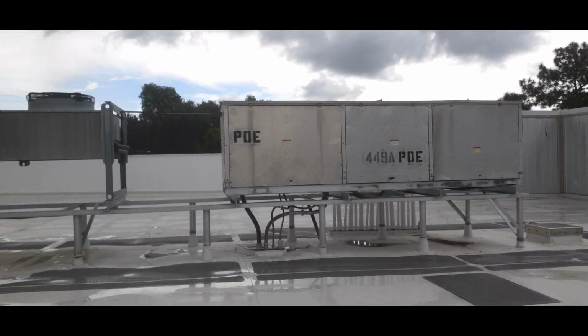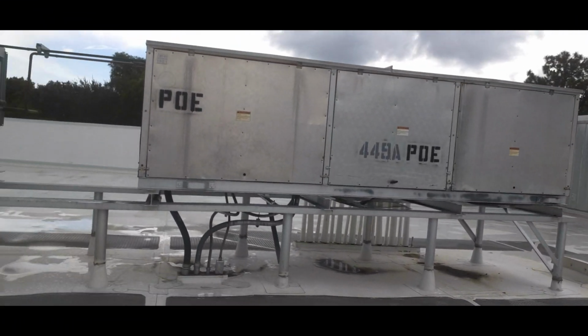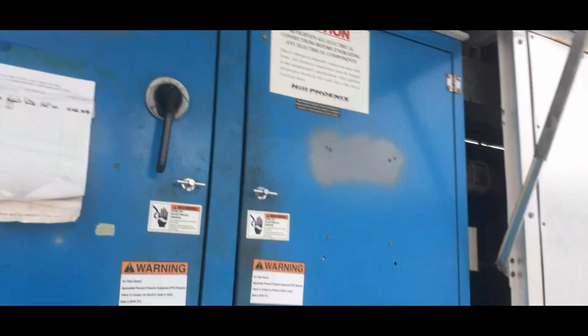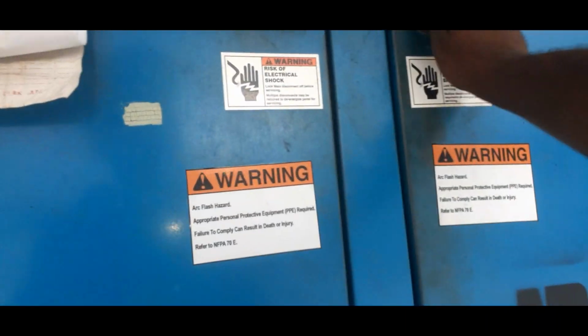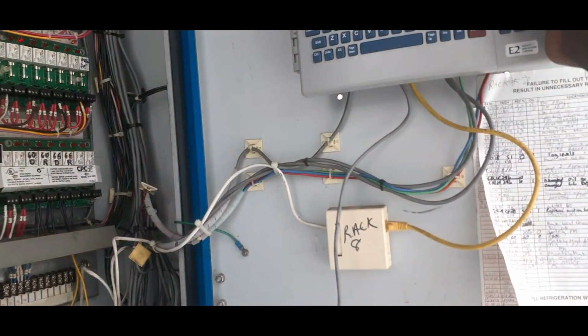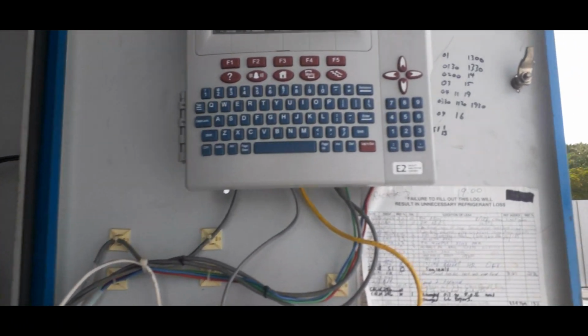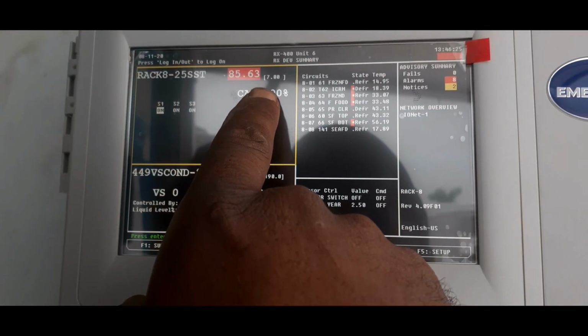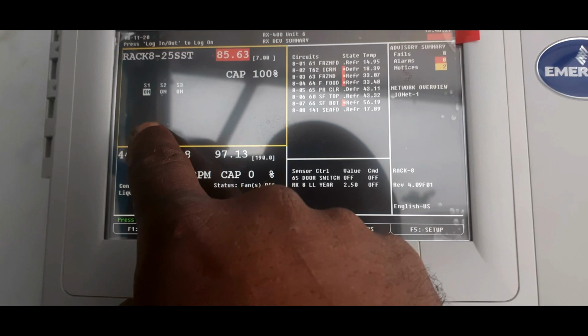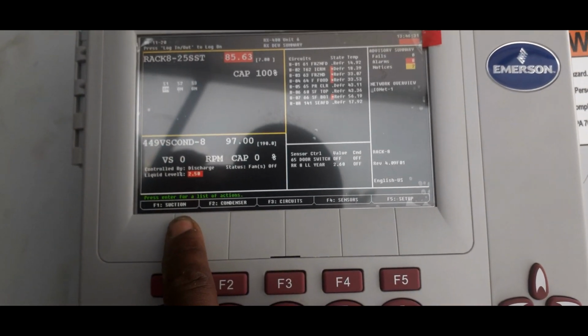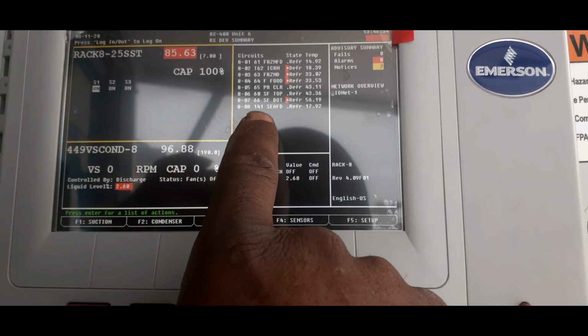Alright, so we got a service call, rack 8, high suction alarm. So far I don't hear anything running. No compressor. Let's get this open. Ooh. So my controller's there. High suction alarm, 85. Suction set point is 7. We're at 85. All compressors should be running. We got multiple cases in alarm, as you can see here.